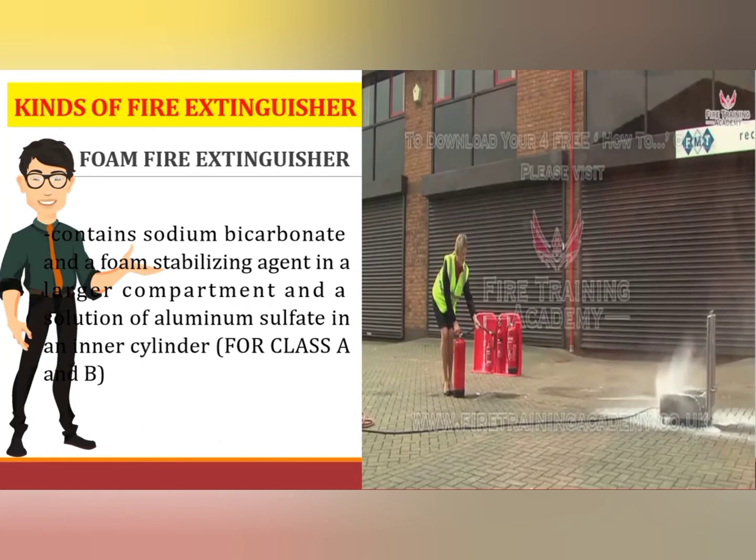The foam extinguishers put out liquid fires by sealing the surface of the liquid, preventing flammable vapor from reaching the air and starving the fire of fuel. They are not suitable for use on free-flowing liquid fires.